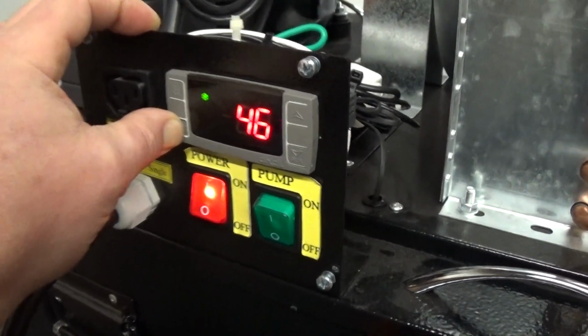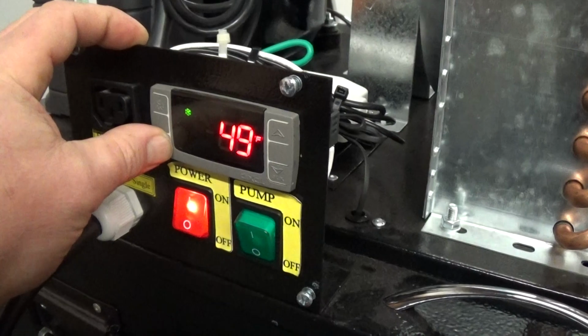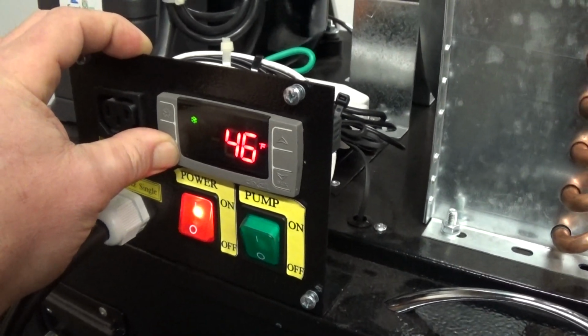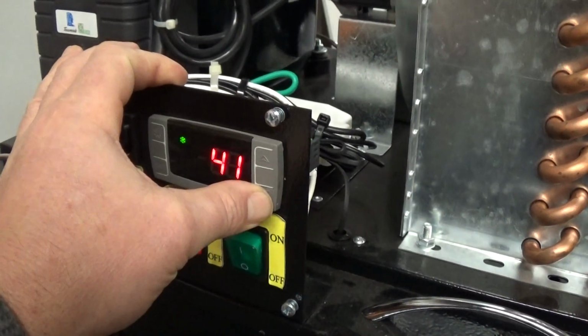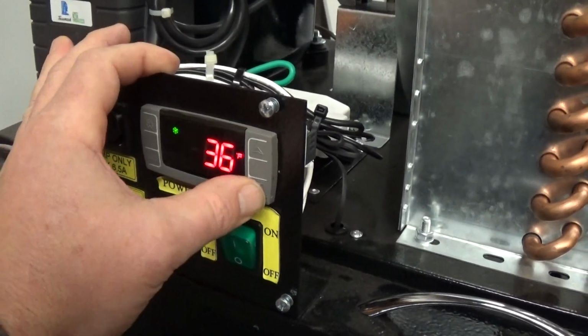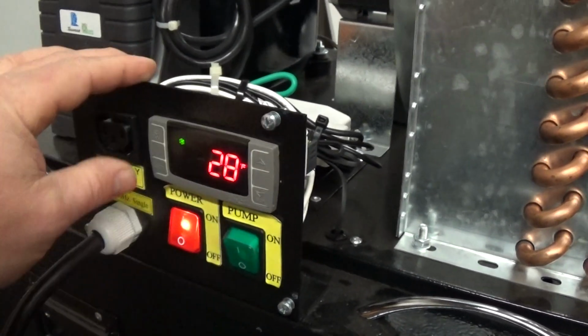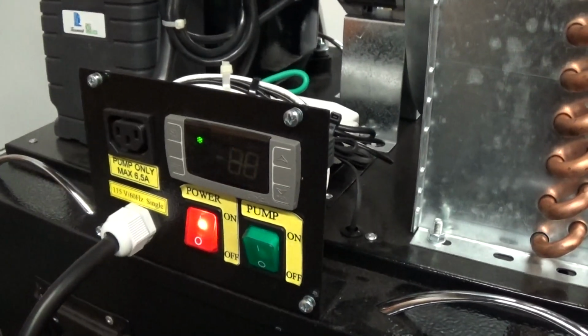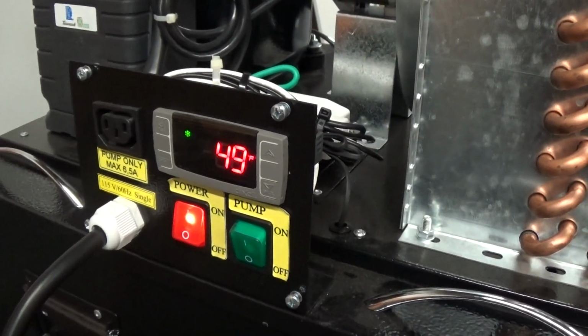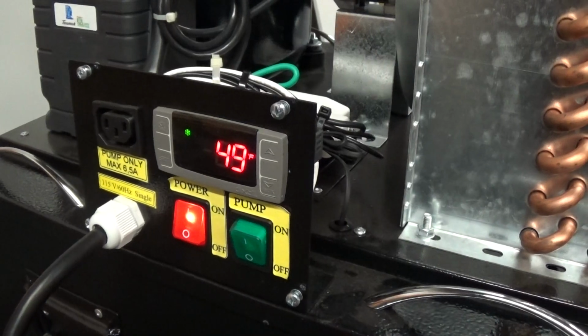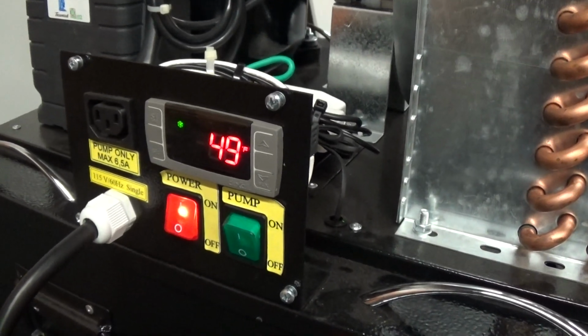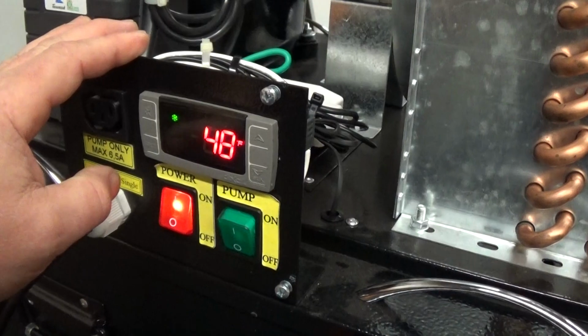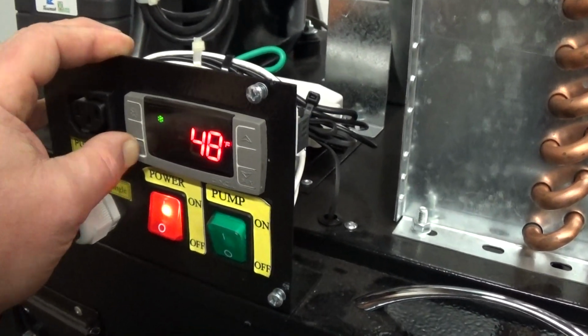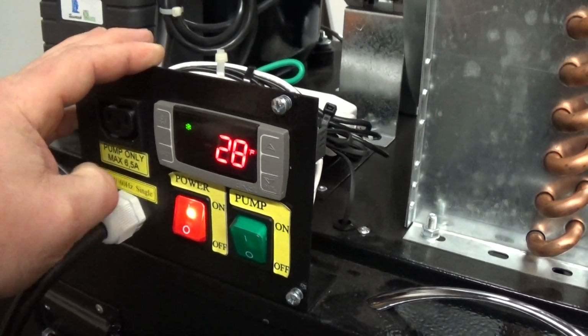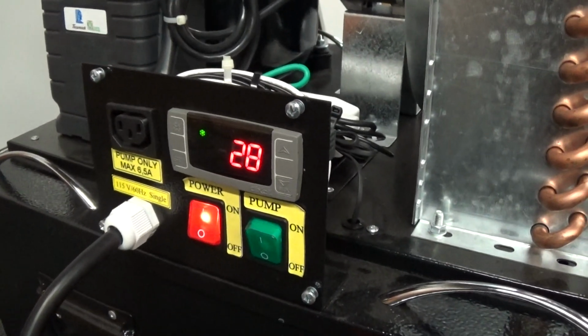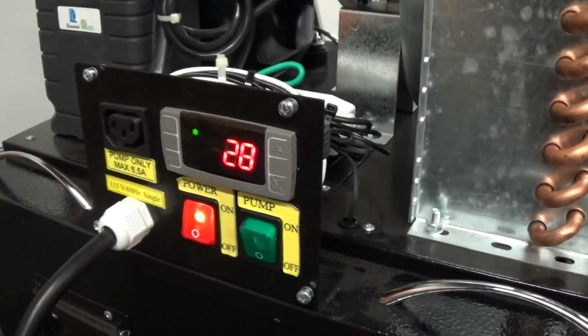See the F flashing there on the right? So you press set for a couple seconds, it flashes, then I press the up or down arrows, and then set again. Okay, so now it's set at 28, and then it defaults back to the process value after a couple seconds. To check what set point you have it set at any time, again, just press set for a couple seconds. All right, and it shows you that I'm set at 28.